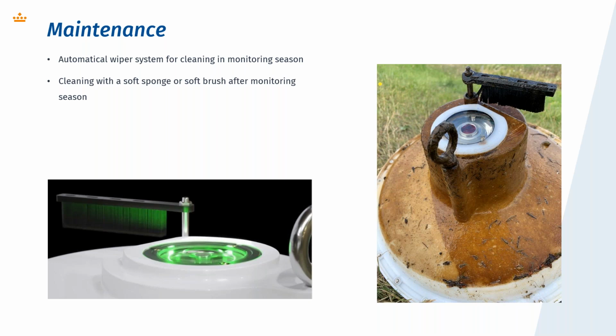How to maintain the buoy? During the monitoring season, easily by an automatic wiper system. As you see on the right, we did a pilot, and after we finished the pilot, we saw that the window where the sensors are behind was still clean, but all the other parts, the bottom part of the buoy, were fouled. Especially with iron-rich water, you can have this kind of picture. But we were happy that the window was clean after 4 months of piloting.